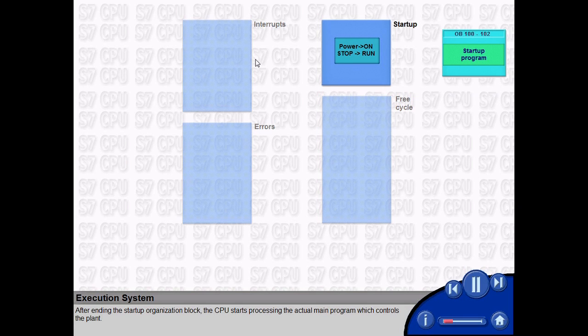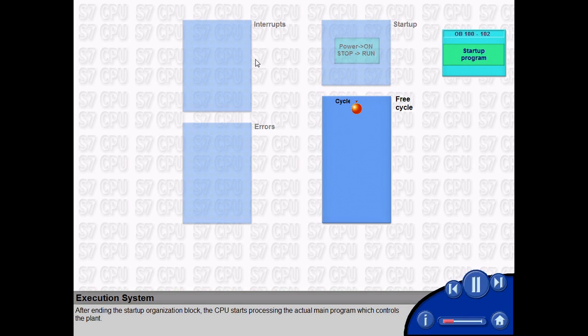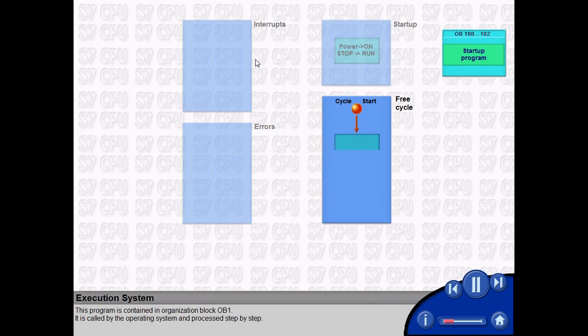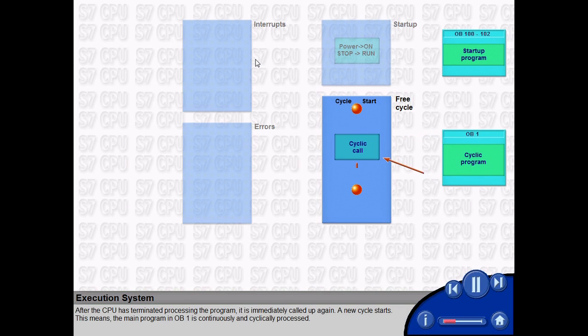After ending the startup organization block, the CPU starts processing the actual main program which controls the plant. This program is contained in organization block OB1. It is called by the operating system and processed step by step. After the CPU has terminated processing the program, it is immediately called up again. A new cycle starts.